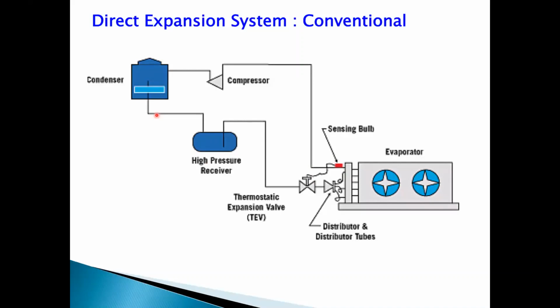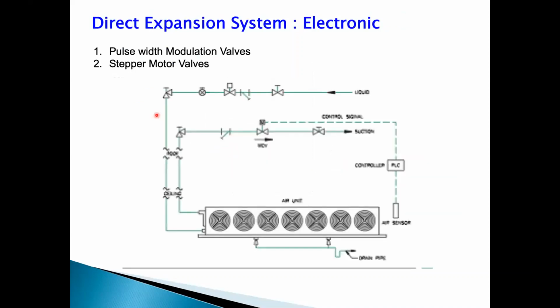But as plants grow bigger and bigger, the volume and quantity of the ammonia becomes a concerning issue, and then the DX systems come back again, and they come with the electronic expansion valves. So what has happened here is that instead of having a thermostatic expansion valve, which was not performing well with ammonia and oil effects, this electronic expansion valve totally operates without anything to do with ammonia and oil.